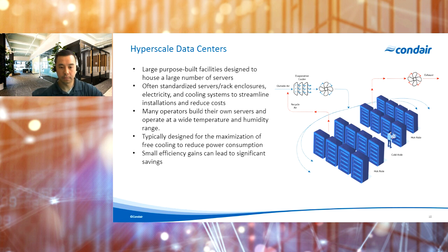Well, these facilities can definitely use all different types of cooling. In the past 10 to 15 years, many of these facilities have been created to leverage economization as much as possible, with one popular option being direct evaporative cooling. Direct evaporative cooling systems allow for very low power consumption and very moderate water consumption when used with low to medium density IT equipment. And given the really large size of these facilities, even small efficiency gains can lead to large absolute savings.